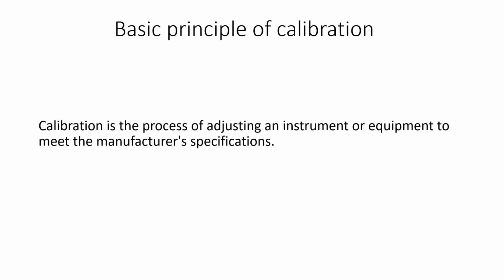Okay, the basic principle of calibration. Calibration is the process of adjusting an instrument or equipment to meet the manufacturer's specification. If you remember, we said that to calibrate something means to check and adjust it if necessary and or possible, when you are working on an instrument or piece of equipment, to meet the manufacturer's specification for input and output throughout a specified range of use or operation, right?